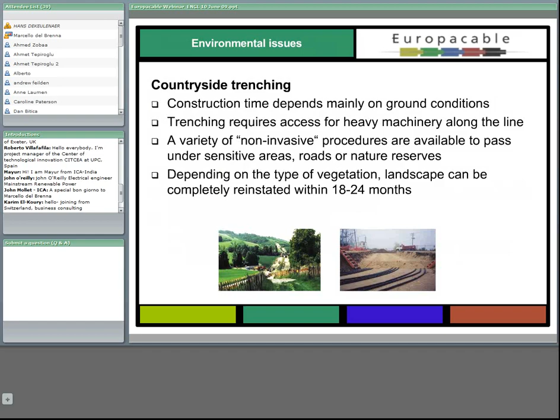There have been discussions about the dangers of heating of the ground by underground cable systems due to the fact that cables run normally at temperatures around 80 to 90 degrees Celsius. In fact, the heat distribution around the cable depends on the backfill material which is selected to be put around the cable. But in any case, the impact is absolutely local and very limited, and with no impact for the wildlife and the vegetation which lives around the cable.